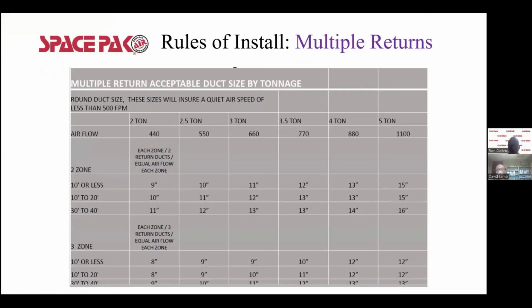Here's that same chart. Okay, and I do want to point out that the other one I changed. This one's a graphic. This 10 to 20, after that, really should be 20 to 30. So that's wrong right there. And to compensate, for instance, when I did my 2.5-ton system, I used this here because 2.5 tons was 625. I wanted 250 CFM per ton, so I used this column, and then I bumped up here, for 12 because there was no 11. So just keep that in mind.